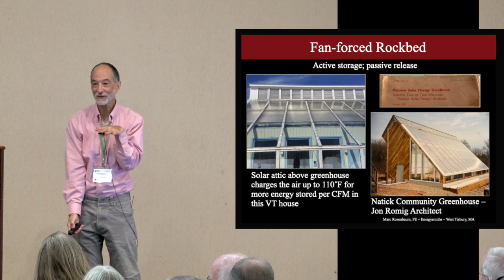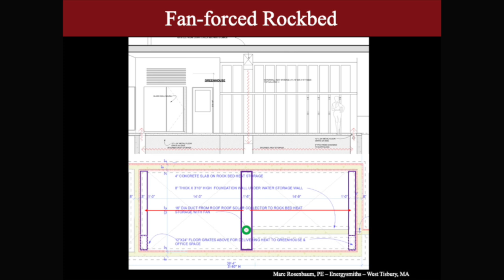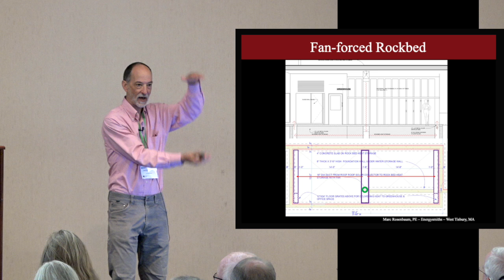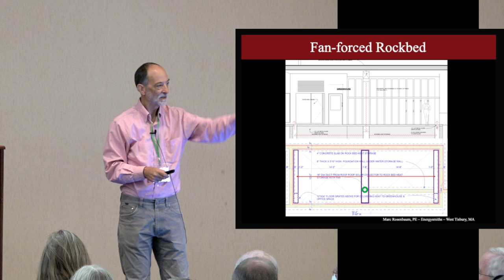Here's a project that's on the boards right now, I'm not sure it's going to get built. It's another freestanding greenhouse, and the bottom image shows the floor and the rock bed. The air comes down the center and goes in both directions. When designing rock beds, it's a trade-off between length and pressure drop, you're trying to minimize pressure drop but still have enough length to hold all the rock you need, playing with height, width, and length. If we ran this along the back going south, we wouldn't have enough back pressure in the rock.